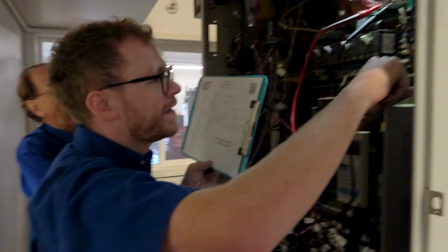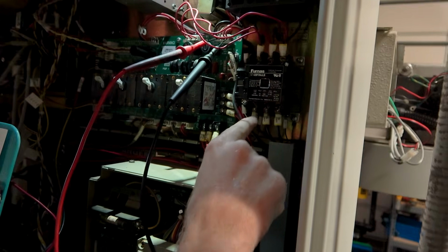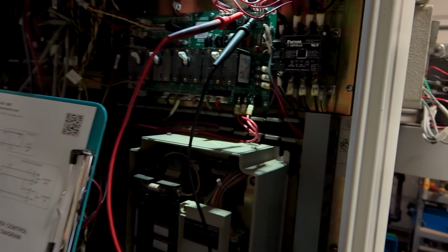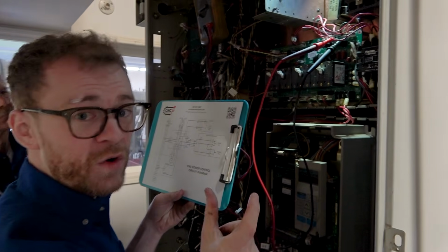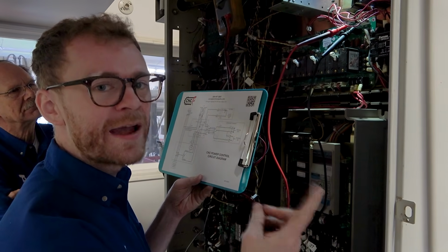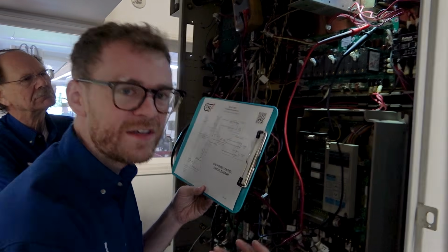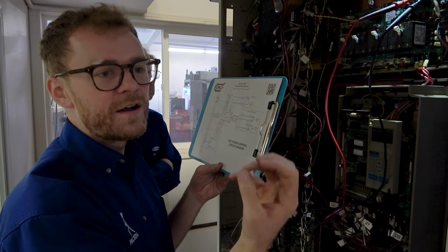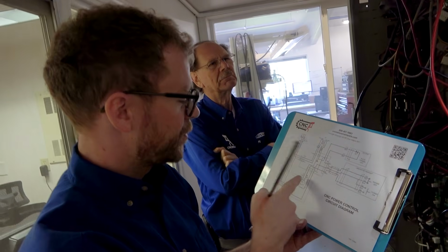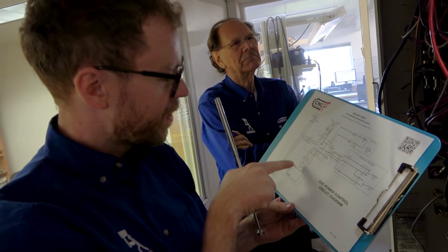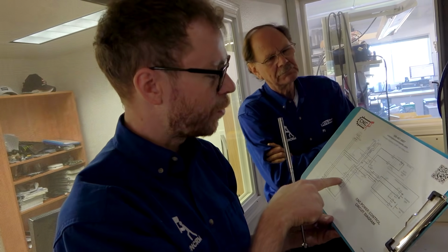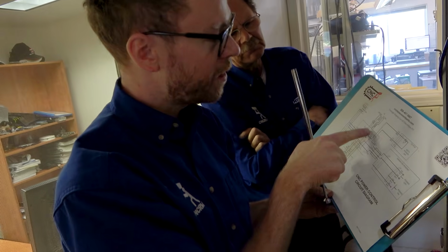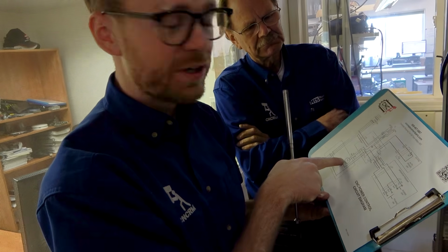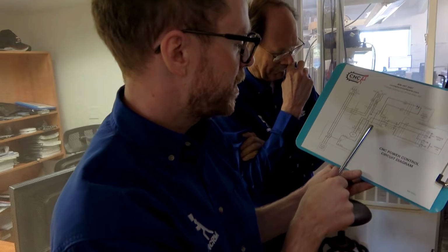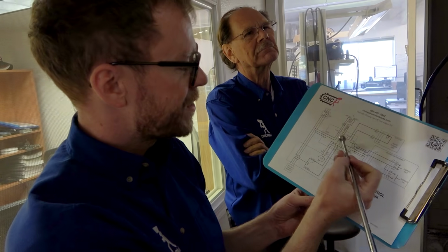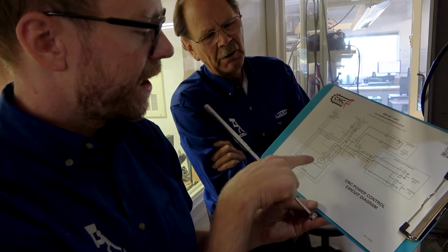Now the coil is going to be the portion of this K1 contactor that sucks it in. When power, electrons, current flow through that coil, it creates a magnetic field. That magnetic field sucks in the contactor. We're going to follow the voltage to the K1 contactor and make sure, because if this contactor wasn't getting any voltage from a bad cable, a bad plug, or from here, then the machine wouldn't turn on. So we're going to go to this P23, and we're going to try to measure from this reference to here and see if we have voltage.